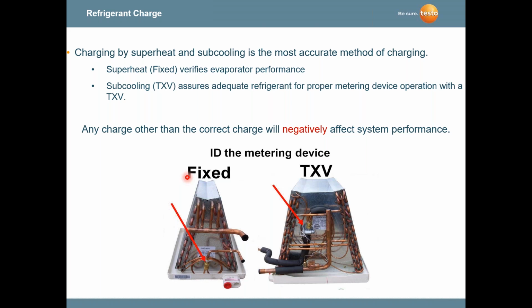Now, as we indicated, we're doing a refrigerant charge. We're using superheat. We're using subcooling. A lot of times on fixed orifices, we may be using superheat, verifying evaporator performance. With a TXV, subcooling assures adequate refrigerant for proper metering. So we have two different types of metering devices that we're looking at today.